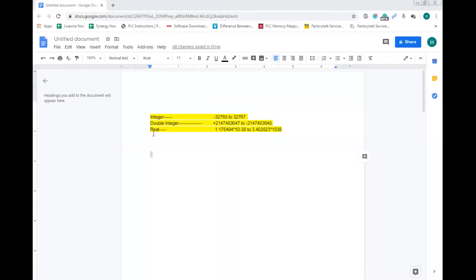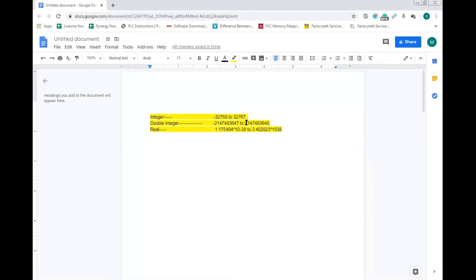For integer we are having minus 32768 to plus 32767. Suppose if you are using an integer block, take an addition block - if your answer is above this value then that overflow bit will be turned on. The same thing is for double integer: the maximum limit is minus 2,147,483,648 to positive 2,147,483,647. And the same thing applies for real value floating point numbers. This is the maximum limit we can use for integer block, double integer block, and floating point block.